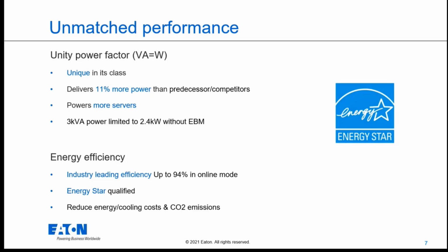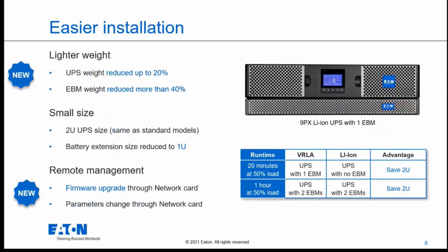Again, I have already discussed the energy efficiency, but you know we are Energy Star. So it's really an industry-leading capability, with up to 94% with the 3 kVA, around 93.5% on the 2.2 kVA and 92.5% on the 1.5 kVA. So these are really very high values for single-phase UPS at this power rating. And of course, the goal is to reduce the energy consumption and all the cooling costs that are linked to that. And of course, the benefit is also a limit of the CO2 emissions.